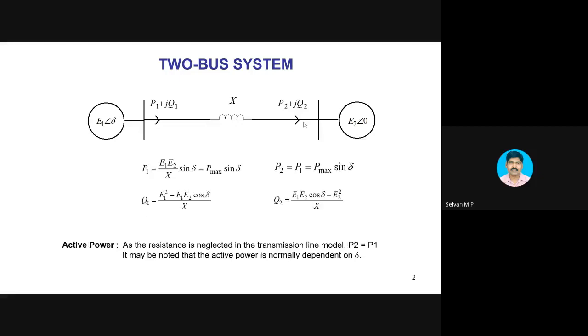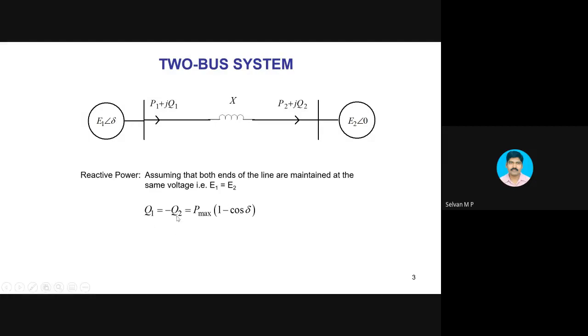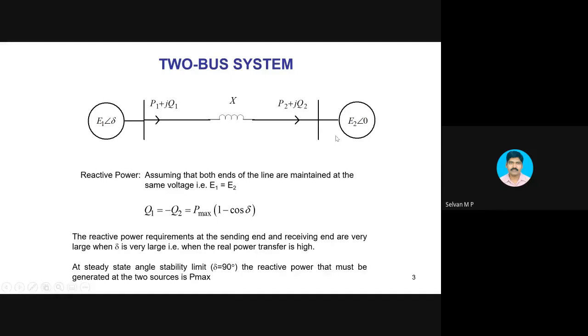If I consider this direction, because look at this. This is P max cos delta minus E2 square by X. E2 square, I can write E1 E2, because E1 and E2 are the same. That's why I'm able to write P max into cos delta minus 1. I consider that P max into 1 minus cos delta as Q1. So Q2 will become negative with the same direction of the arrow mark. So what does it mean, this negative sign? As I said, the negative sign indicates that there is a power flow from this bus into the transmission line, similar to Q1. Q1, the reactive power flows from this machine into the transmission line. Similarly, Q2 is negative, means again the reactive power flows from this machine into the transmission line, or from this bus into the transmission line.